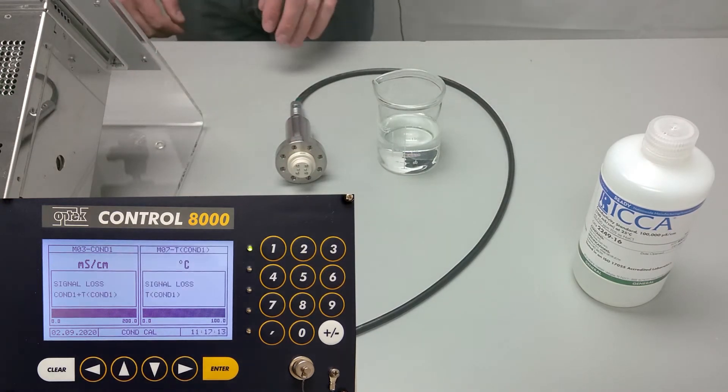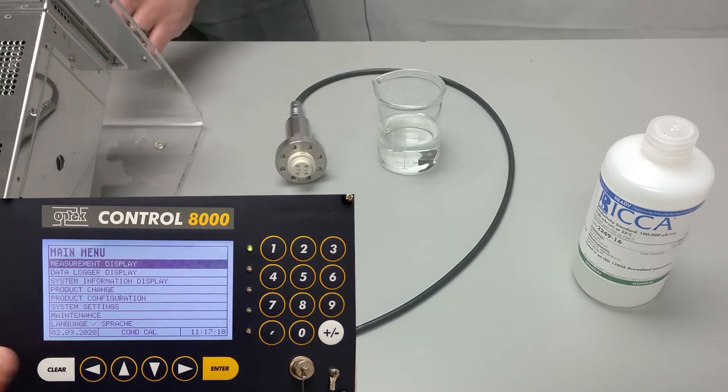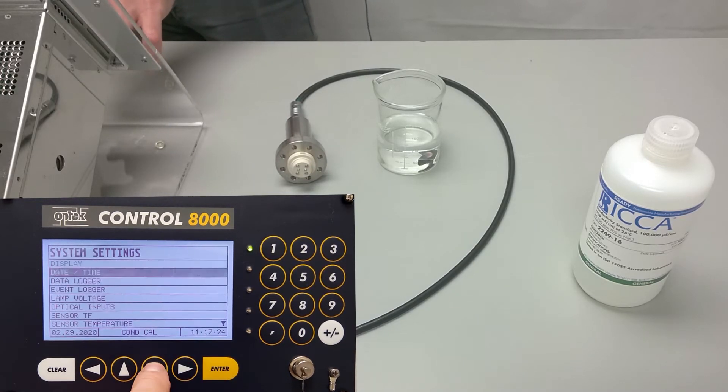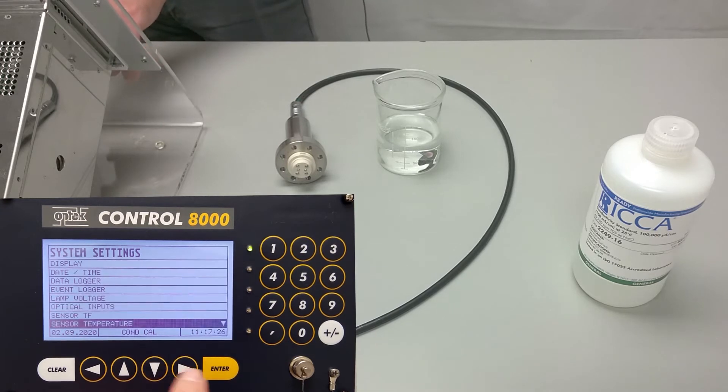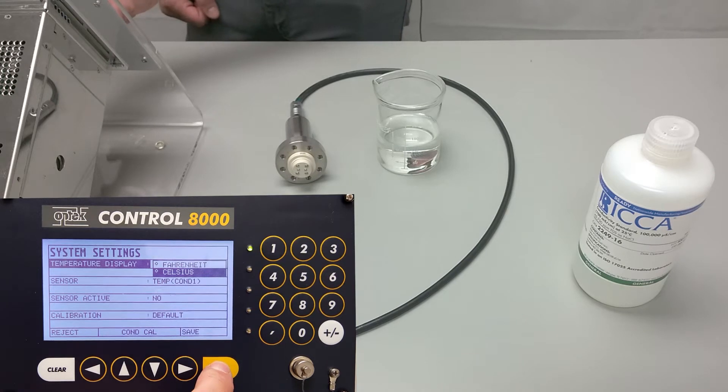The first step is to ensure that the conductivity sensor and temperature RTD probe are set to active. We'll press clear to get to the main menu and scroll down to system settings, scroll down to sensor temperature, and if we wanted to change from Fahrenheit to Celsius, this is where we could do that.